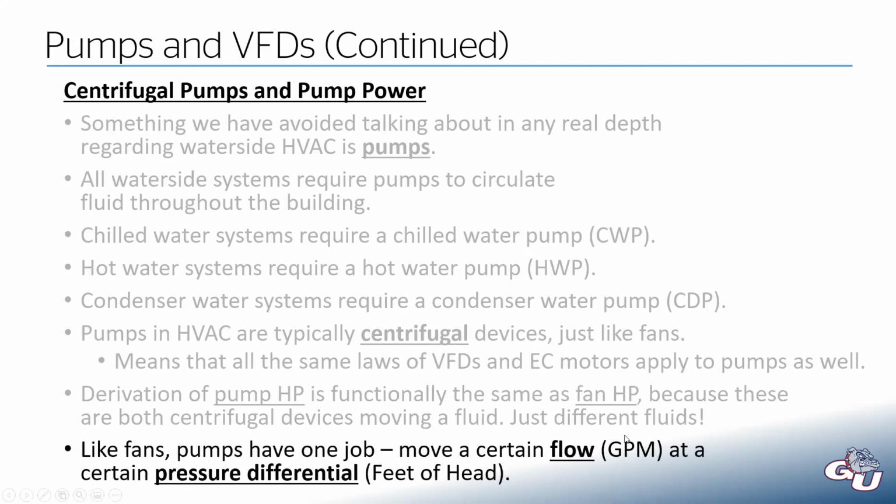Similar to fans, pumps have one job: move a certain flow at a certain pressure differential. Analogous to a fan, which has one job, which is move a certain flow in CFM at a pressure differential in inches of water column. So it's doing the same thing, moving some flow at some differential. It's just doing it in different units.